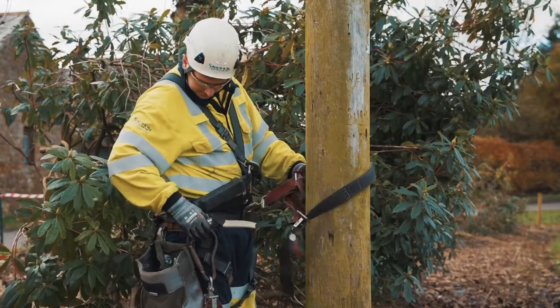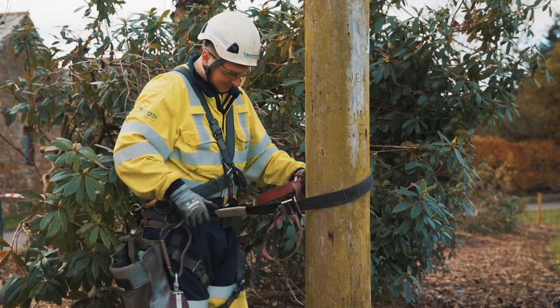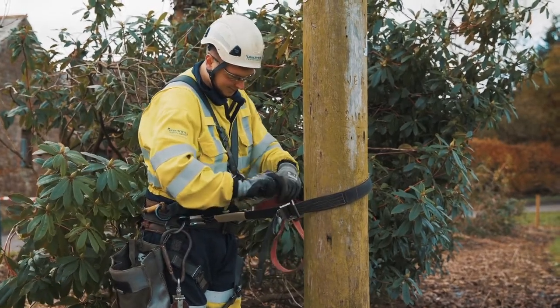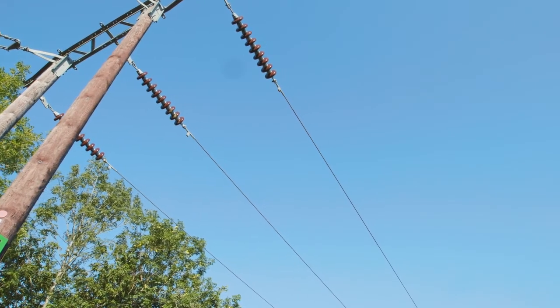So in November 2019, we carried out HV faults on the overhead line. These included phase-to-phase and phase-to-earth tests. These faults were most successful, and the software was able to detect to an accurate location within 100 metres of the actual fault that was applied. Earlier this year, we carried out a low line test where we lowered, again in a controlled manner, the HV conductor of one phase to 1 metre and 2.5 metres above ground. Once the line was re-energised, the data was collated from all the devices within that trial circuit.